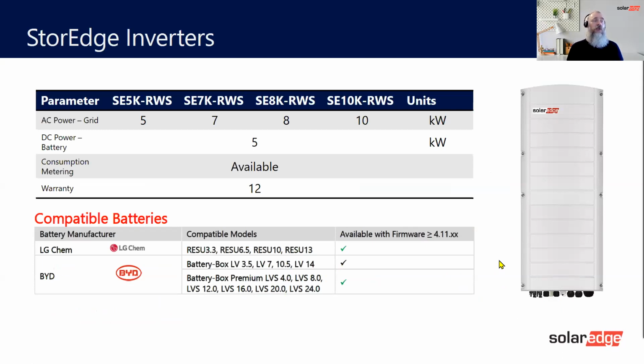So the inverter itself is a 5, 7, 8, and 10. It discharges at 5 kilowatts. So if you're using the AC coupled version, you really only need the 5 kilowatt version. If you're using DC coupled or you've got PV, then obviously 10, 8, or 7. But if you're only using AC coupled, because the battery inverter discharges at 5 kilowatt, then you only need 5 kilowatt.